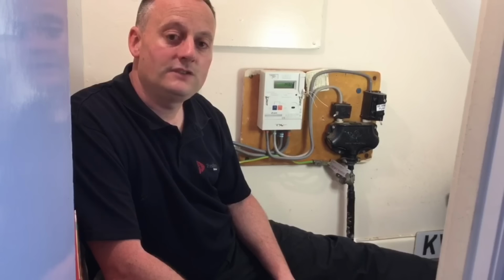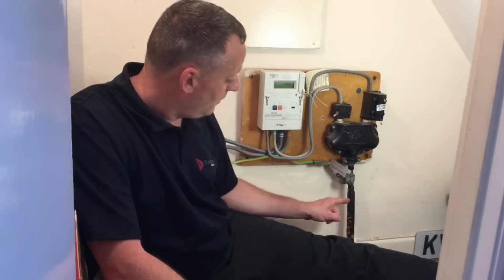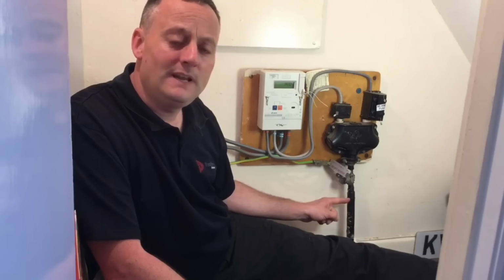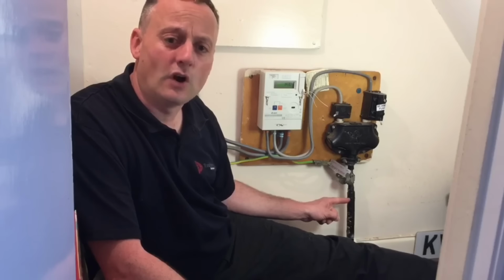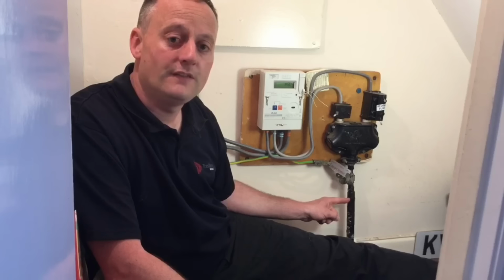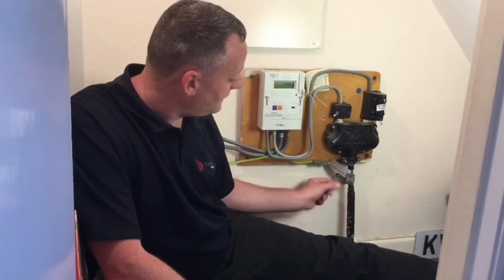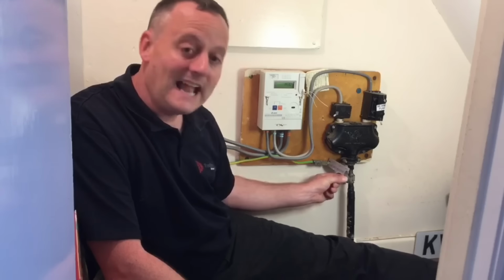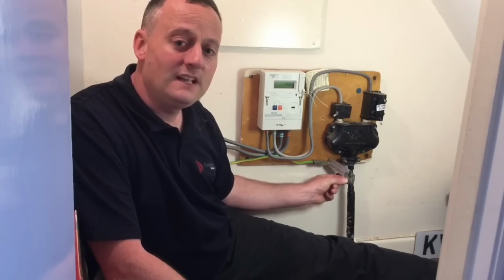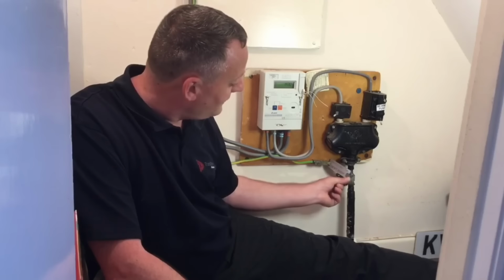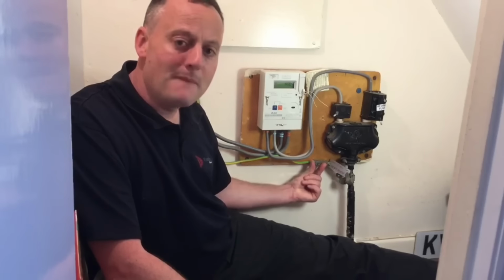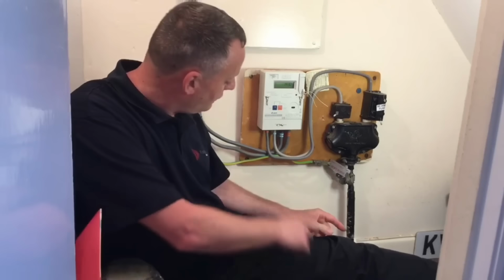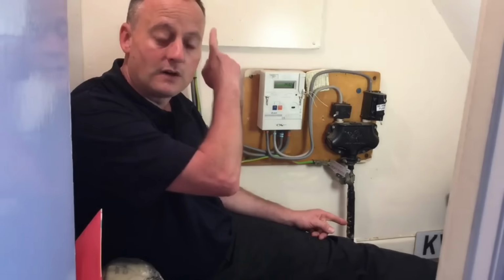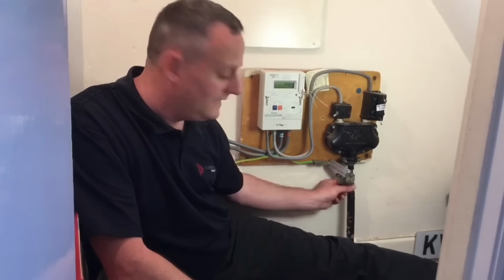So to work out the earthing arrangement we have this time, we'll look at the supply authority's cable incoming into the bottom of the cutout, which is here. We can see it's considerably larger in size, physical size that is, than the one we had on our previous earthing arrangement. And we can quickly identify here this braided section of the sheath of the incoming supply cable then terminates into our MET, our main earthing terminal, and goes off in the 16mm earthing conductor to our consumer's unit. So we've got a slightly different arrangement here.